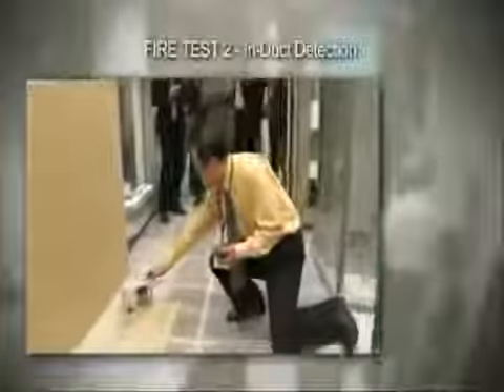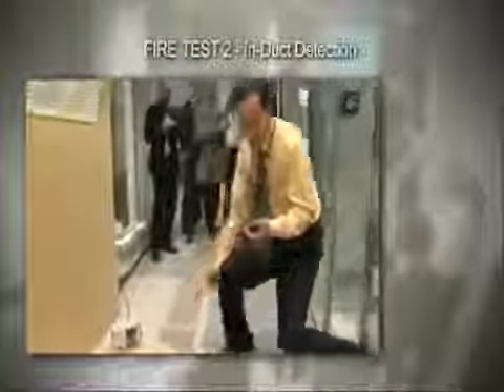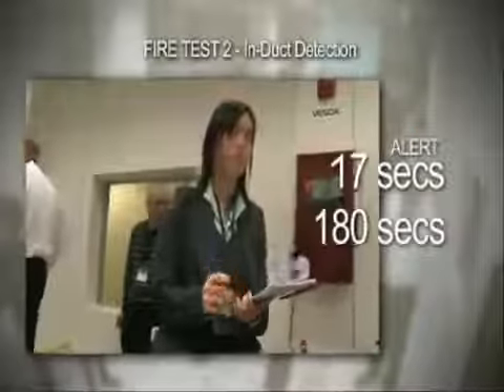In Test 2, a PVC cable fire is lit on the floor next to the return air grill. The smoke is drawn up into the return air duct but does not reach the ceiling-mounted detectors. The VESDA Laser Compact sampling in the duct goes into alert at 17 seconds. After 180 seconds, the point detector located on the return air grill has still not detected the smoke.